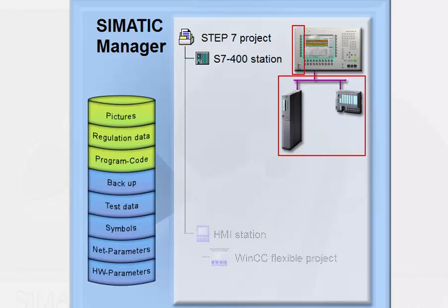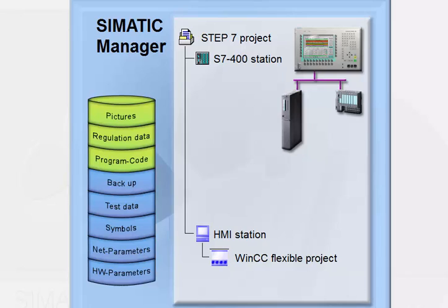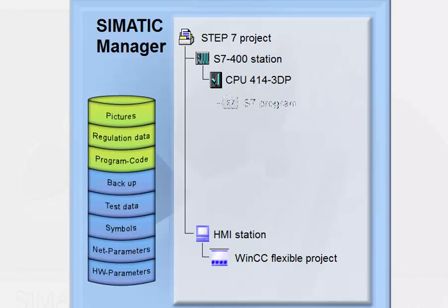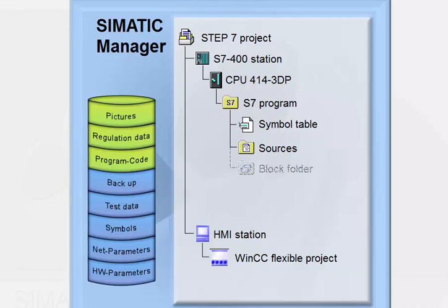A project comprises mainly the following hierarchically structured objects: one or more stations containing all the data of a controller. This includes, on the one hand, the configuration data with the station's hardware structure and the parameters of the modules used, and on the other hand, all user program data contained in the CPU object. The CPU object has the connections of the CPU assigned to it, and the S7 program contained in the CPU. The S7 program object contains the symbol table, the program source folder, and a folder containing the user program blocks with the executable code.